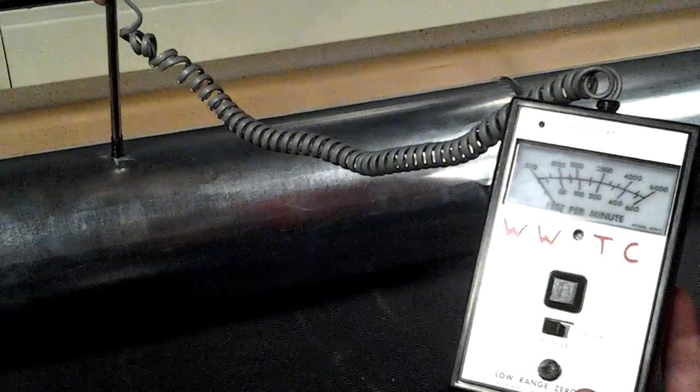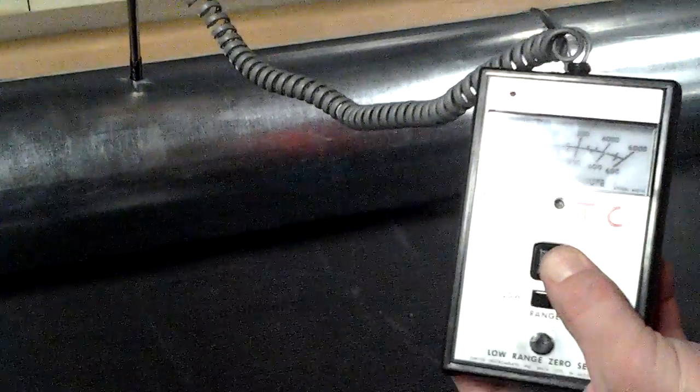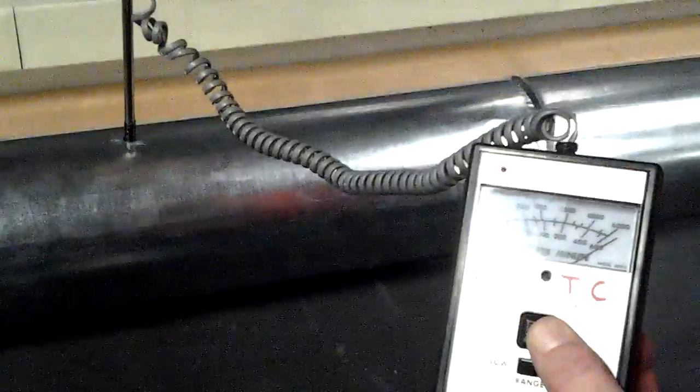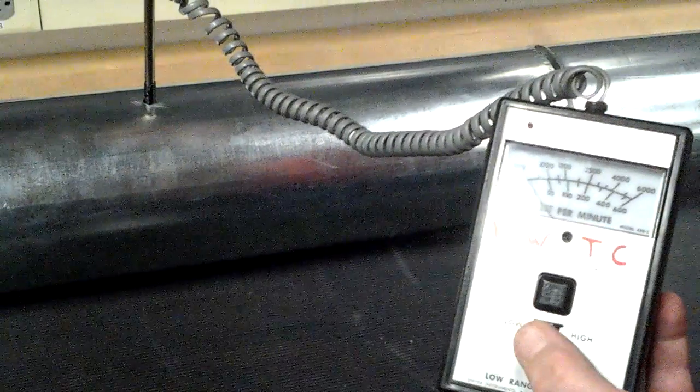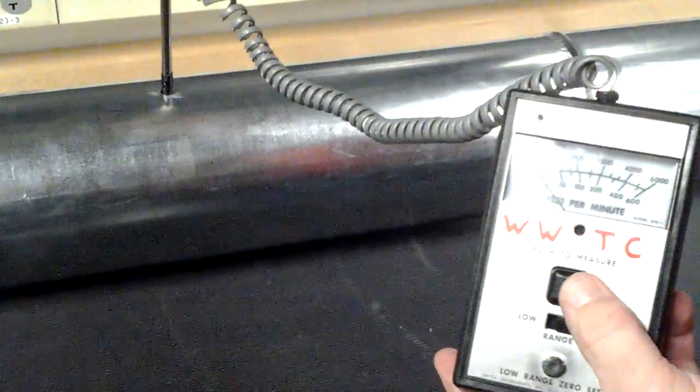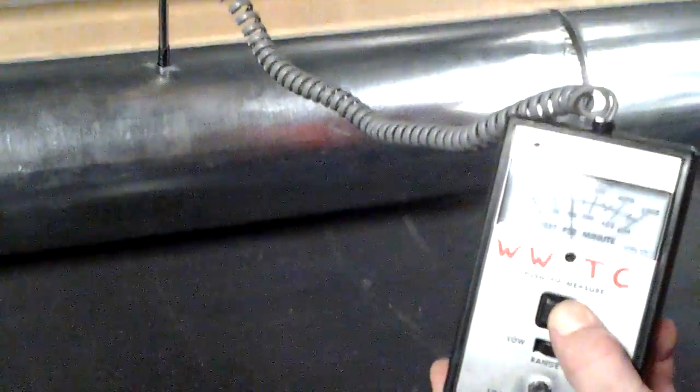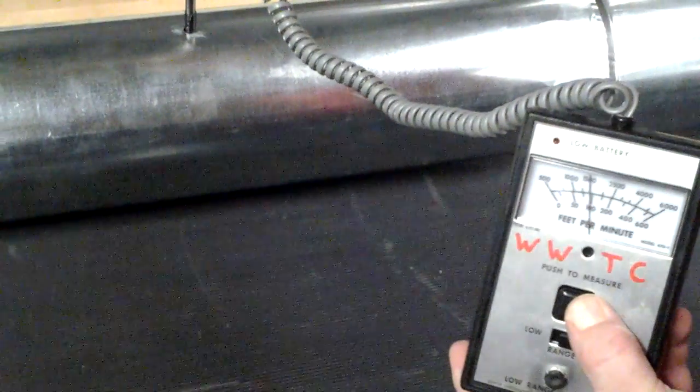Depress the push to measure switch. After a momentary warm-up period, read the measured air velocity on the appropriate scale. With an unknown velocity, measure first in the high range. This time, the meter indicates 1,500 feet per minute.